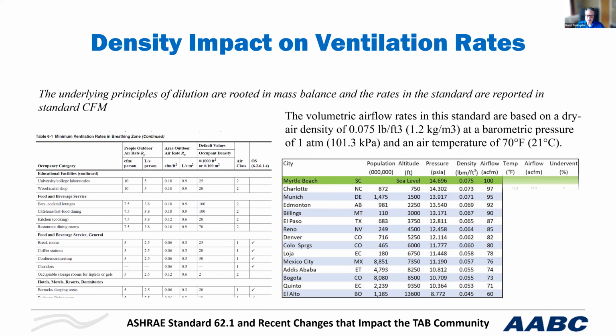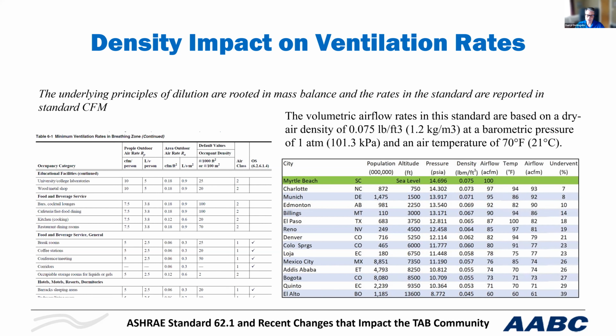And as the temperature increases, you also have that effect. So what I did is I listed the cooling design dry bulb temperatures for each one of these spaces, and I compounded the effect. And if you look, it's significantly worse. I have actually seen design documents in Colorado Springs that were 23% underventilated because they took the 62.1 rates as actual for the location without any correction. So, this is an important thing.